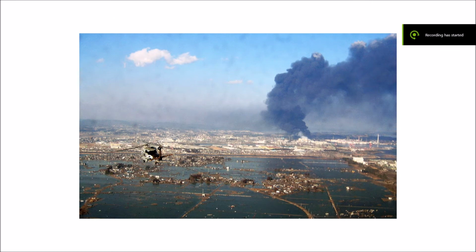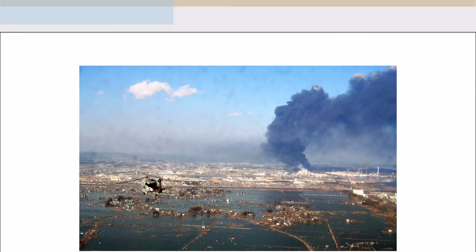One of the biggest drawbacks to nuclear reactors is that natural disasters could destroy the facilities which aid in maintaining the nuclear reactor. In Fukushima, Japan, for example, a tsunami hit the nuclear power plant site, causing the main electrical power supply of the plant to be shut off. The backup generators turned on, but soon after another tsunami hit, which flooded the site, causing the underground generators to shut off. Due to the lack of power to pump water to cool the reactor, the nuclear reactor overheated and eventually blew up. This caused the surrounding area to be radioactive and restricted for public access.